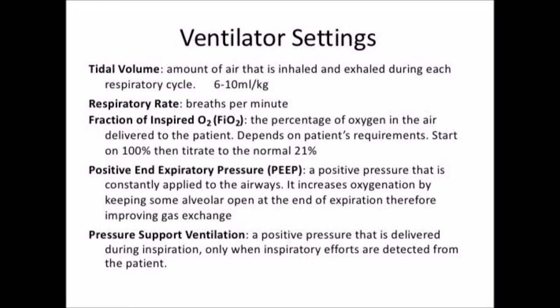Additional settings include positive end expiratory pressure, or PEEP, which is a positive pressure that is constantly applied to the airway — it increases oxygenation and prevents alveolar collapse — and pressure support, or PSV, which is a positive pressure that is delivered during inspiration only when inspiratory efforts are detected from the patient.